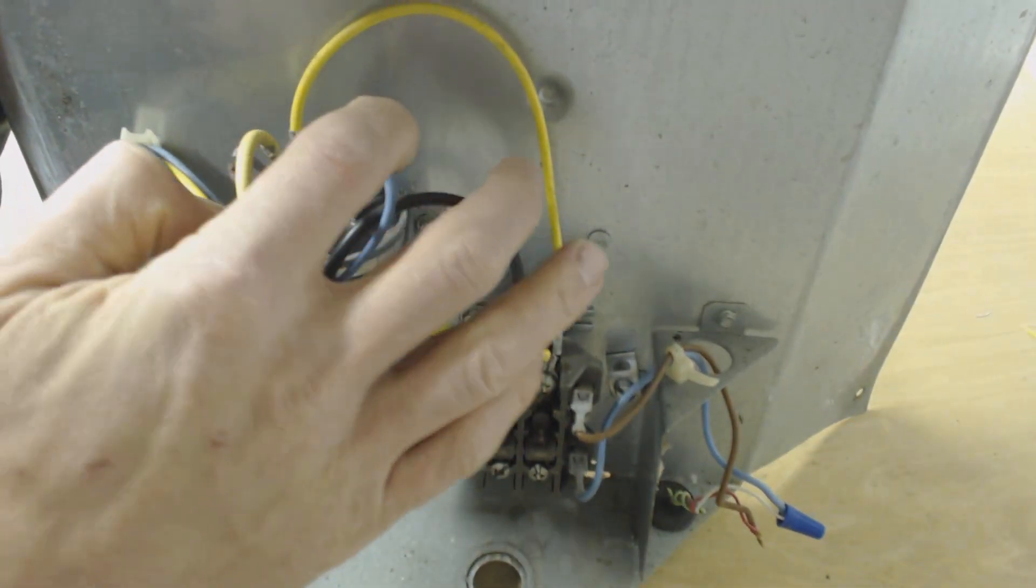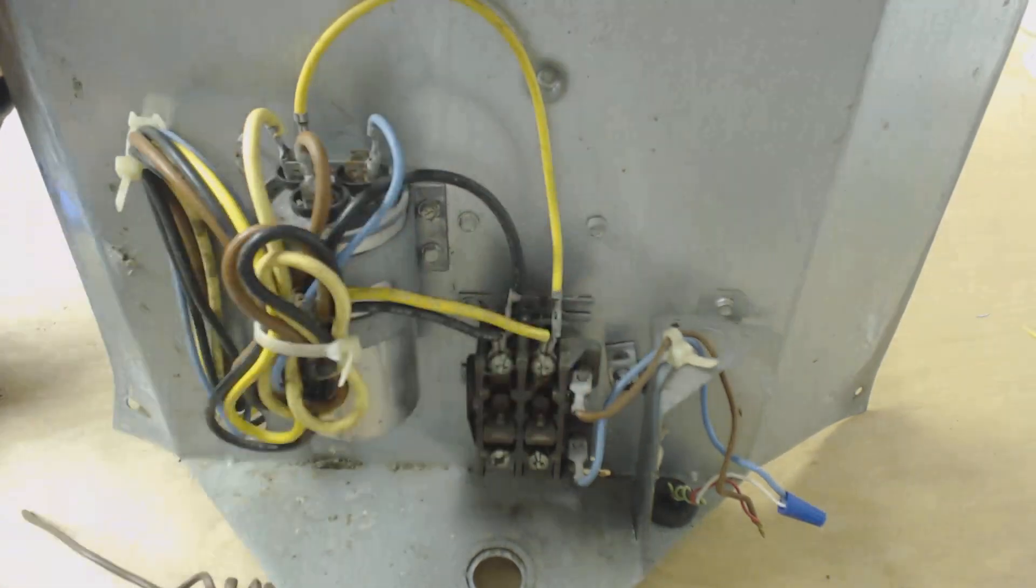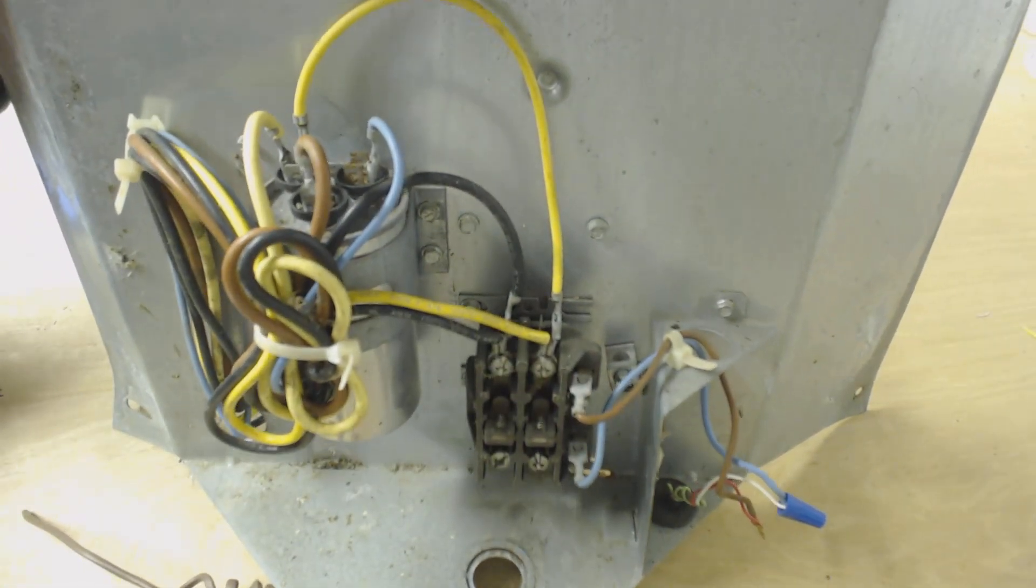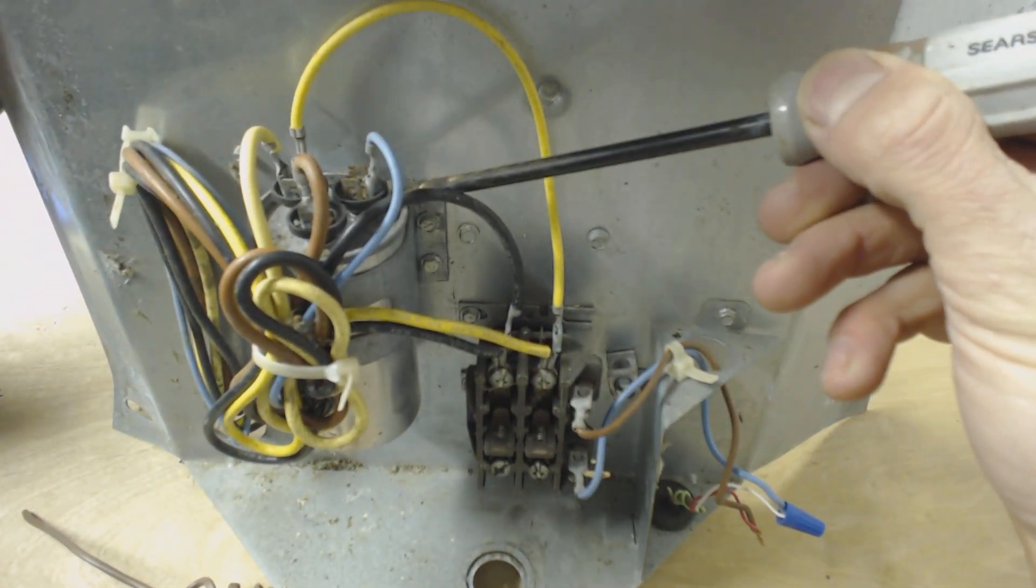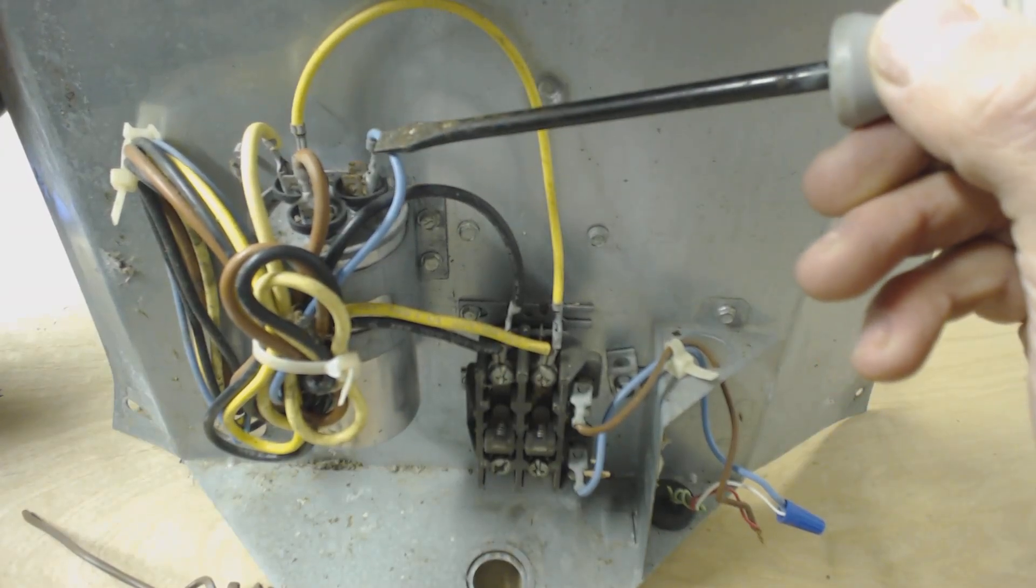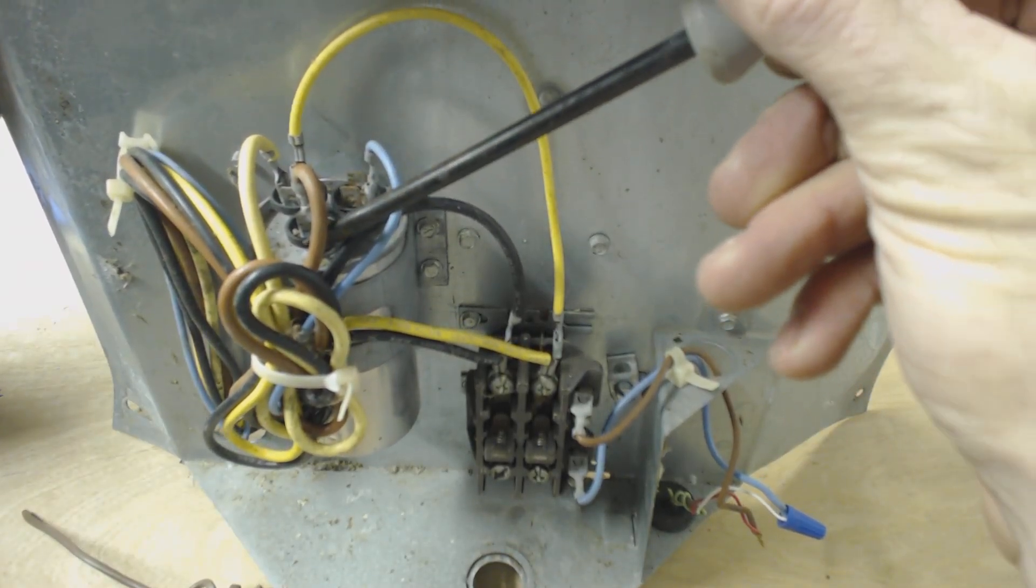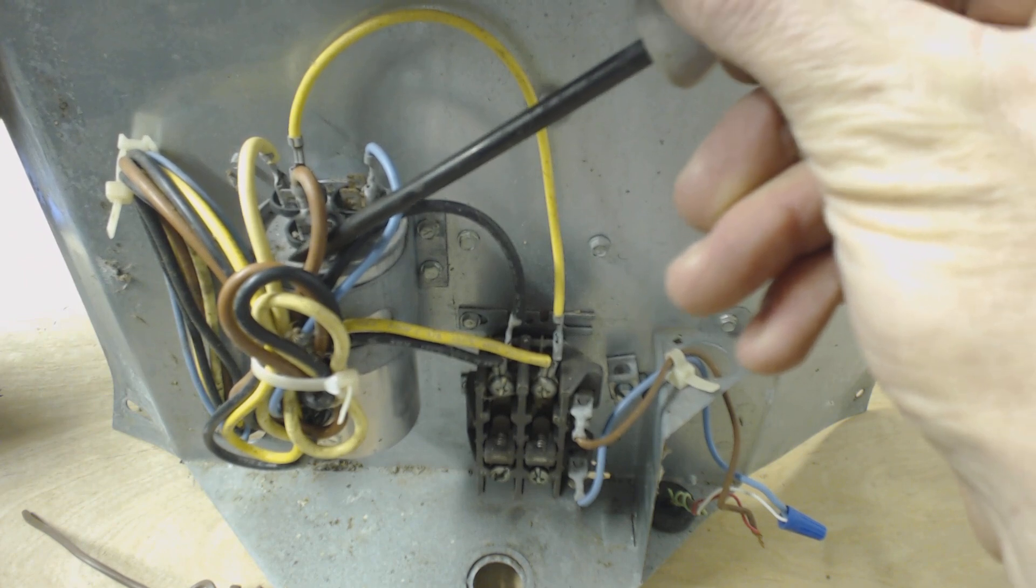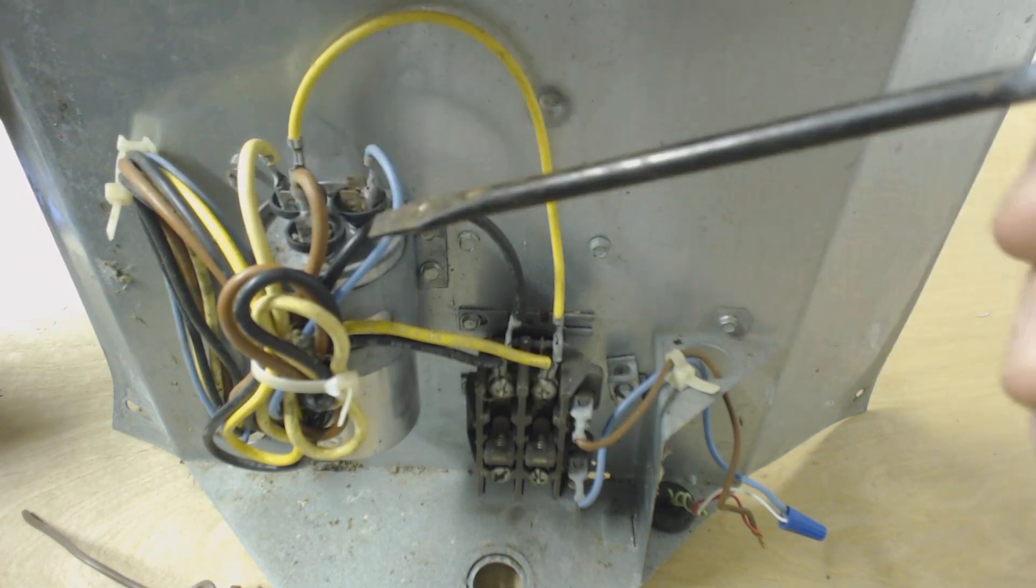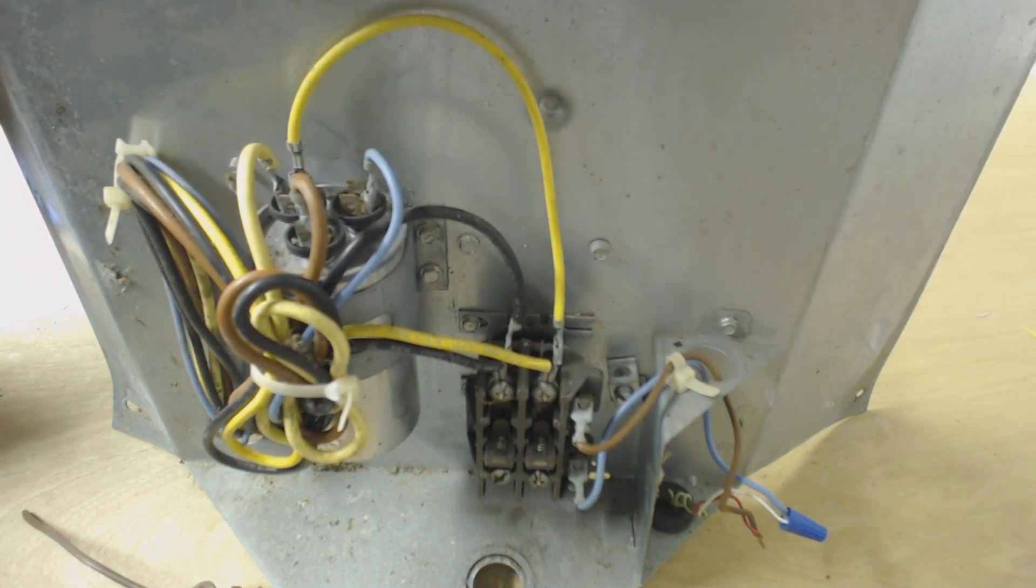The blue wire right here, right next to it on the capacitor, it says Herm, and that goes to the compressor. This brown wire right here says F or fan, and that one goes to the fan that's on the top of the outdoor condenser.